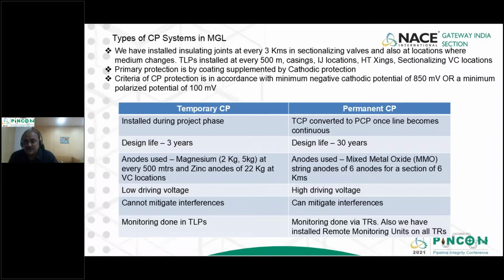The primary protection is coating, and we supplement it with cathodic protection. The criteria for cathodic protection is in accordance with a minimum negative voltage of 850 millivolts, and that's the first criterion, or a minimum polarized potential of 100 millivolts. So this is our condition for CP protection. The temporary CP is installed during the project phase, and after the project is completed, we install the permanent cathodic protection once the line becomes continuous.